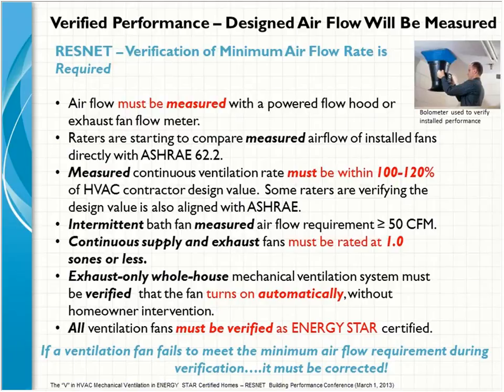Well, that's no longer the case with ASHRAE 62.2, or most ventilation codes. It would be required not just that you buy a 50 CFM fan, but that it actually be measured and be able to perform at a 50 CFM level. Or it has to be tested and perform at the level required by ASHRAE 62.2 for the whole house ventilation requirement, which we're going to talk about how to calculate or find using the chart. But it's no longer acceptable just to install equipment rated for a certain CFM.